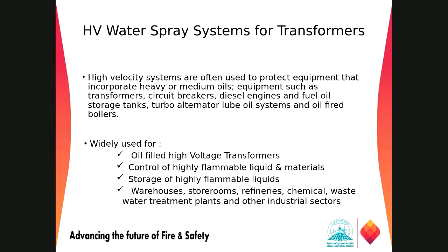So this requirement does not come from NFPA 15. NFPA 15 is just one standard that lets you know how to install this system. The requirement comes from NFPA 30 or maybe some other API code, and should be determined by the process safety engineers or process design engineer. The design engineer will give you the exact requirement to install such a system in your facilities.